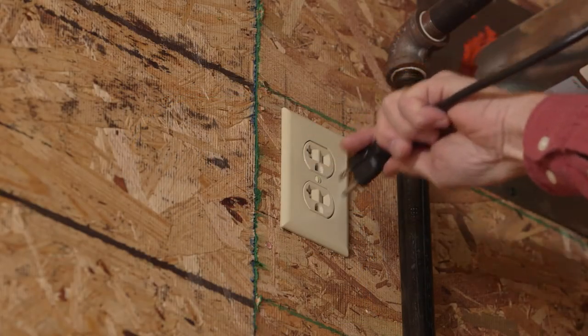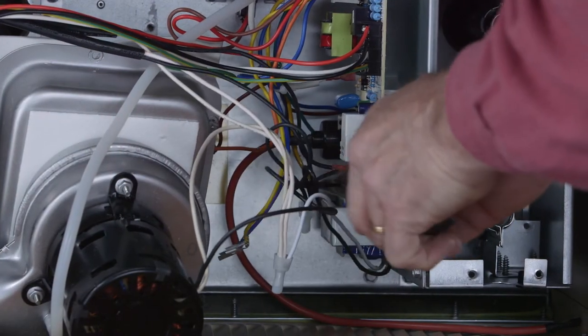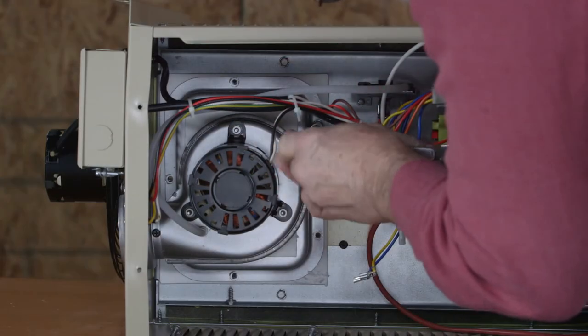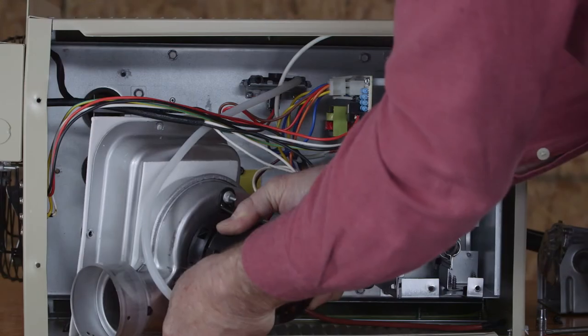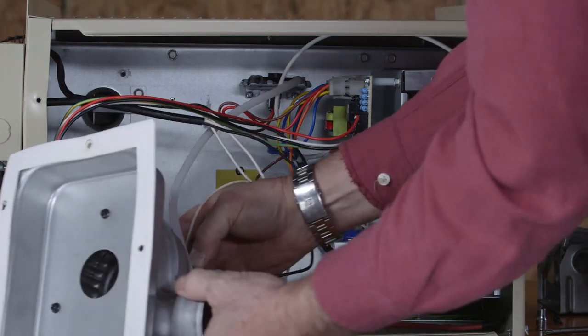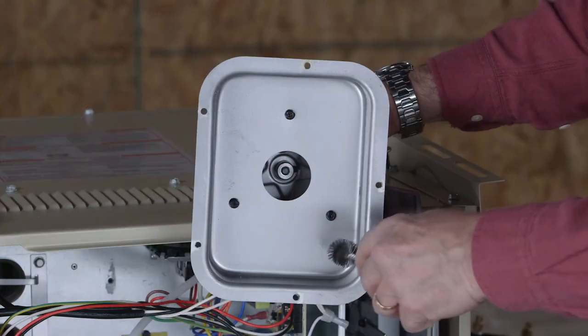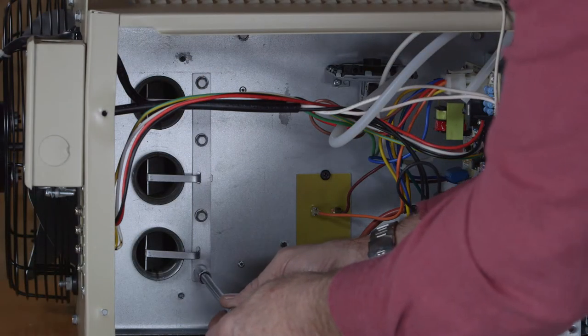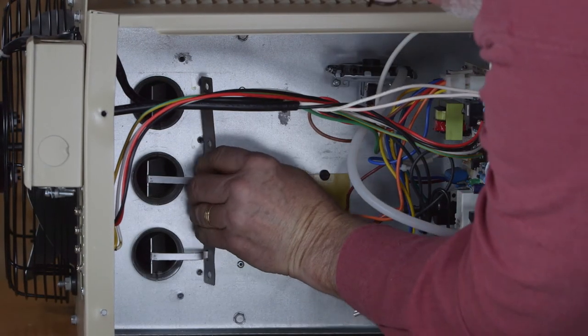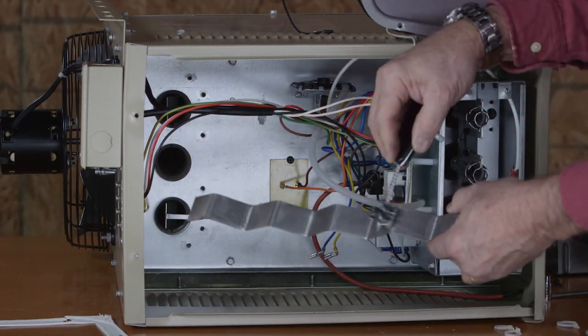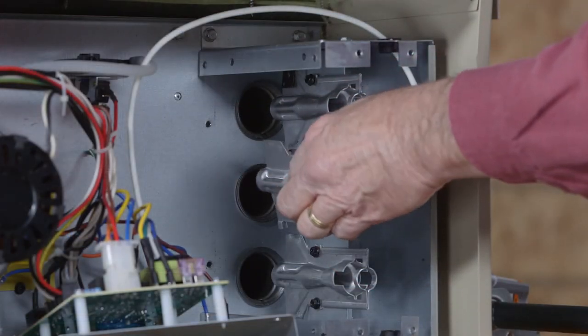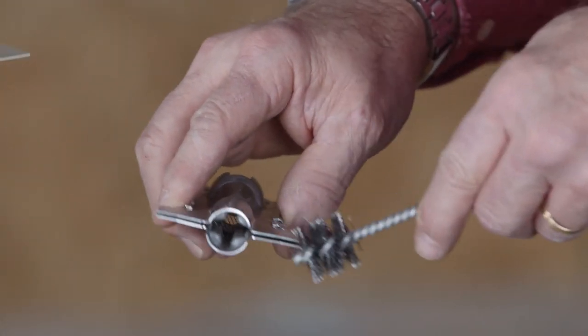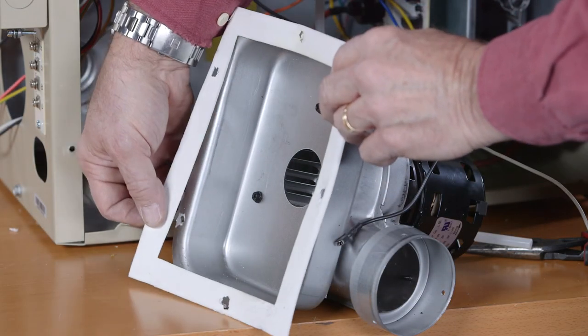The flue passages and flue box should be inspected and cleaned prior to each heating season. To do so, in sequence, turn off electrical and gas supplies. Disconnect combustion air blower wiring. Remove screw securing flue box to the unit. Remove flue box. If necessary, remove blower assembly from flue box. Clean flue box with wire brush. Remove turbulator retention bracket and turbulators. Clean turbulators with wire brush. Remove burners as previously shown. Clean tubes with wire brush. Reassemble unit.